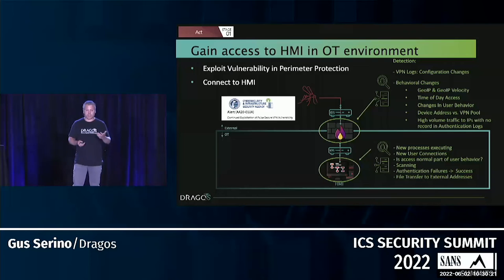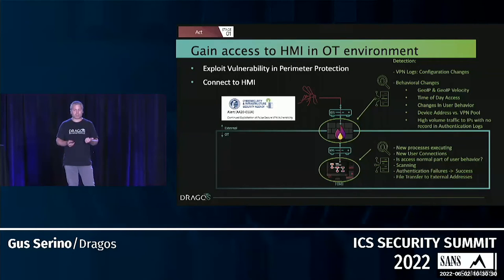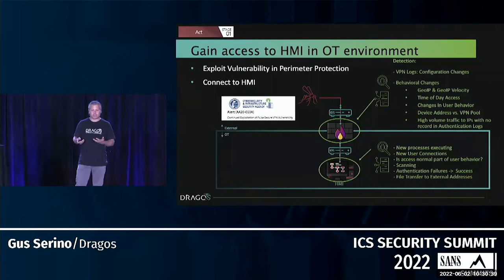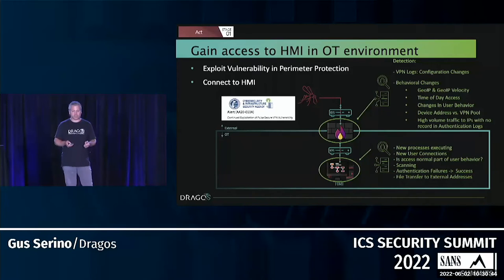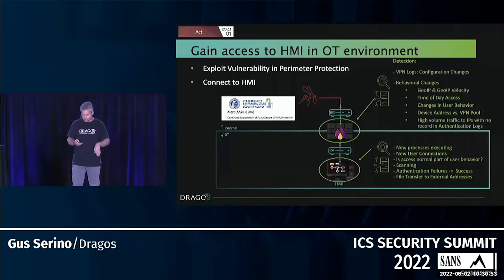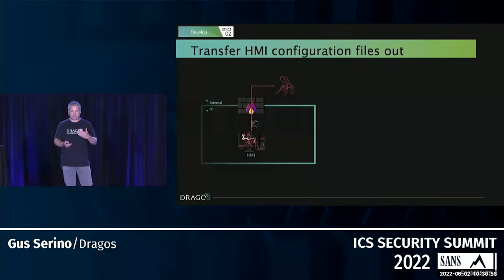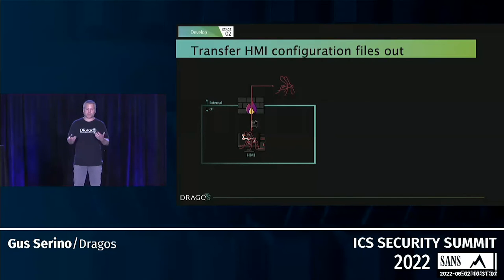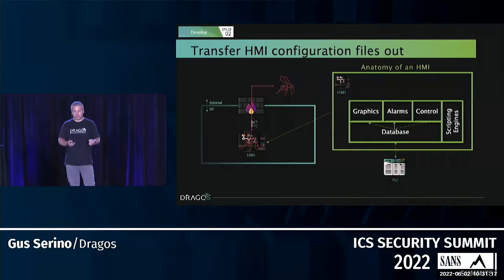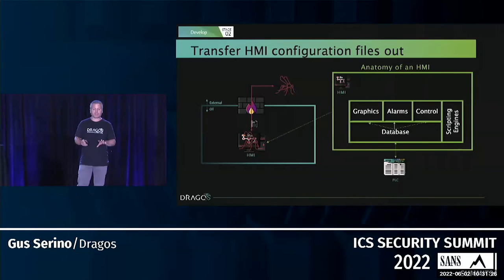Moving down into the HMI: the adversary gets in with legitimate credentials and pivots to the HMI. For detection there, look for new processes executing on the HMI, new user connections, unusual scanning activity, authentication failures followed by success indicating brute force, and file transfers to external addresses. At this point the adversary takes the HMI files and exfiltrates them — this is where we pivot from ICS kill chain stage one to stage two, with ICS knowledge and interest now in play. HMIs alone give an adversary enough tools to cause harm to the process.